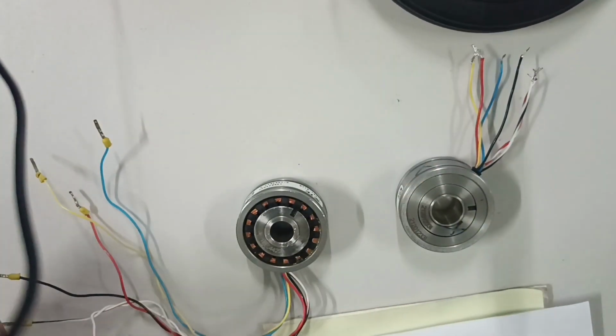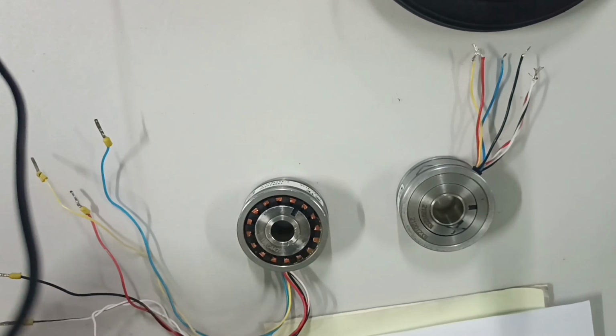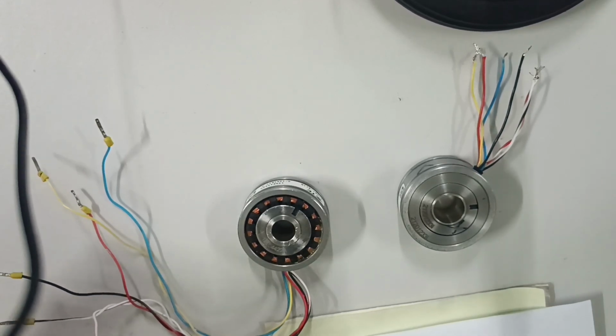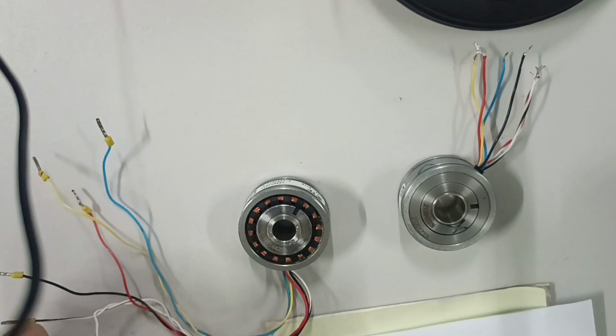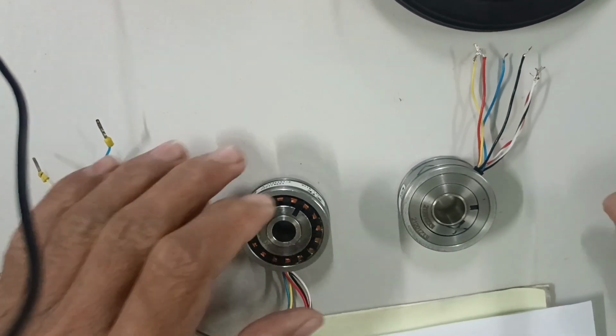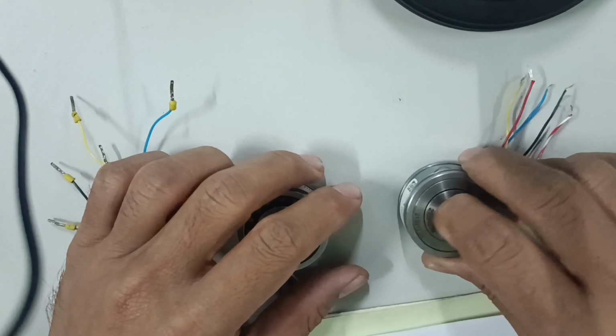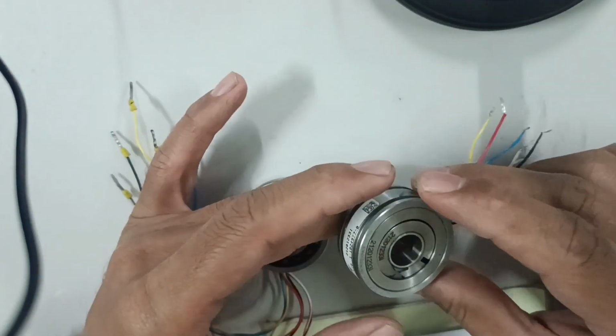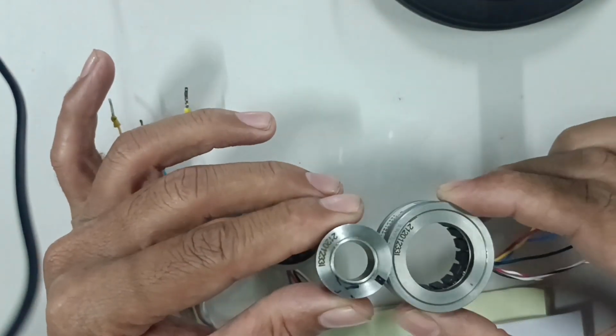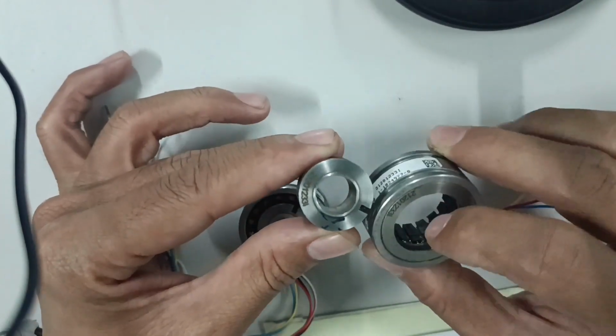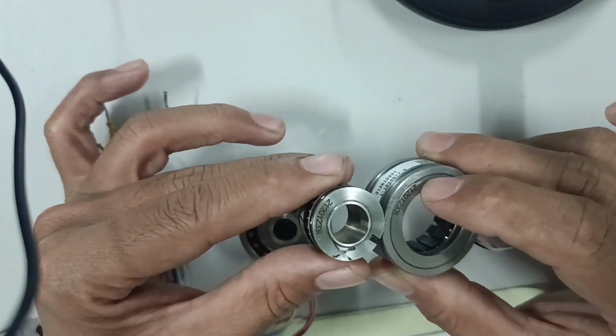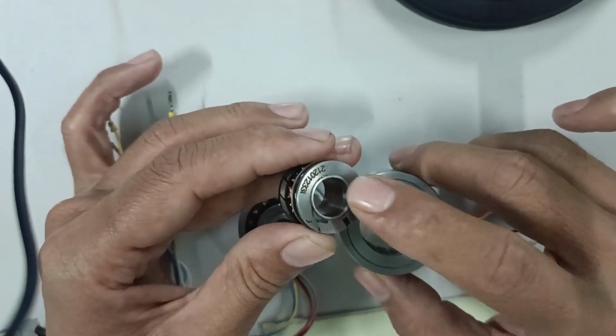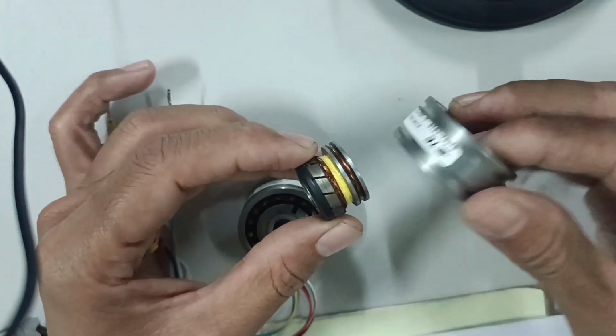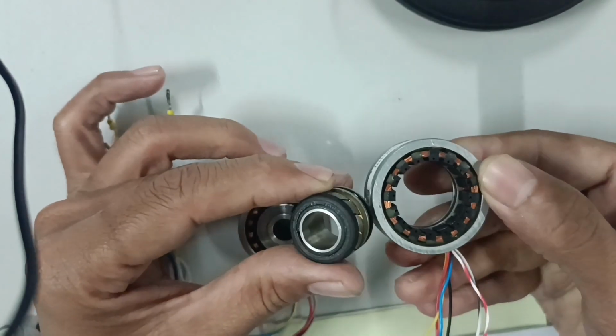So I'm just cleaning all the gear oil from the resolver side, and now you can see the clean resolver. I have completely opened it from inside the motor. Before I start, I have mentioned in the video details: before troubleshooting the resolver, check if any resolver-related error is showing in your controller or HMI, such as resolver fault, position feedback error, over temperature, or speed fluctuations. If you find any of these four problems, then you have to follow my troubleshooting steps.